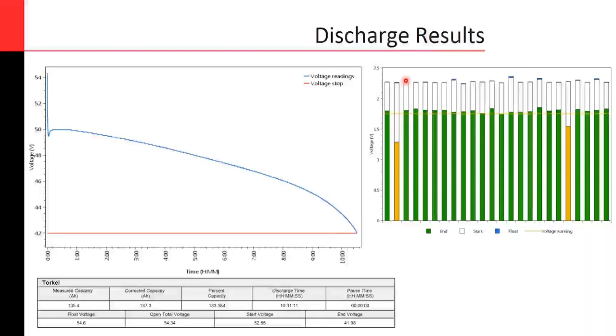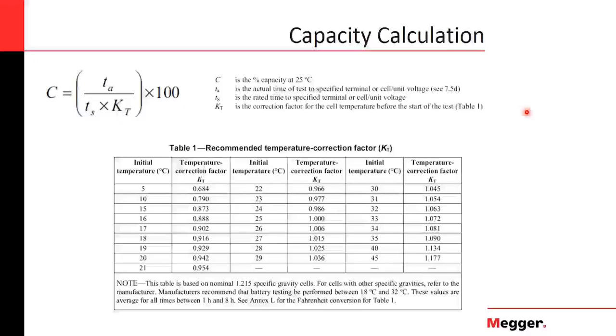The way to calculate the capacity is a basic formula. From the table, you have an expected time, an 8-hour duration or 4-hour duration, depending on what you select. That is this term here, the expected time. And once you run the test, you have the actual time, how long the test lasted. So in this case, for example, in the previous slide, it would be 10 hours and a half here, 8 hours and a half here, and this 8 hours here, and this term will be the correction factor depending on the temperature at the moment of starting the test.